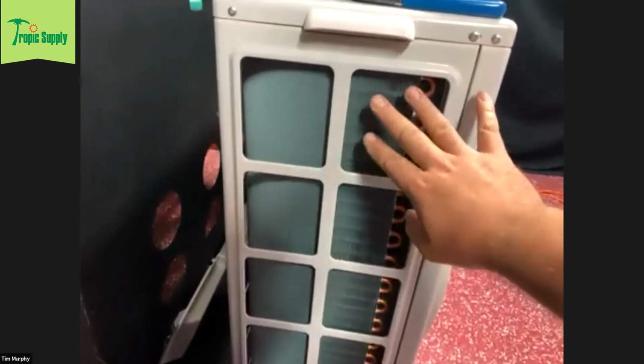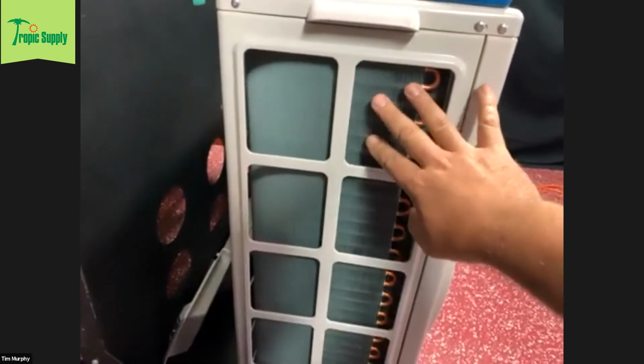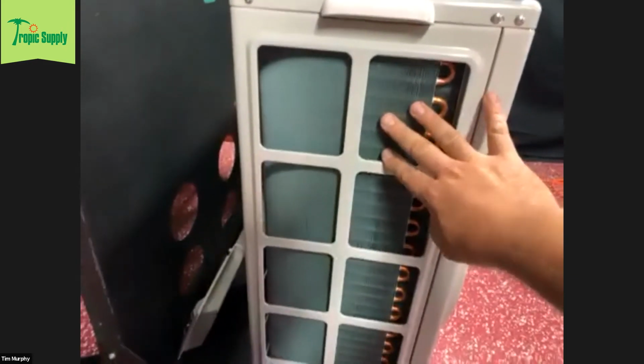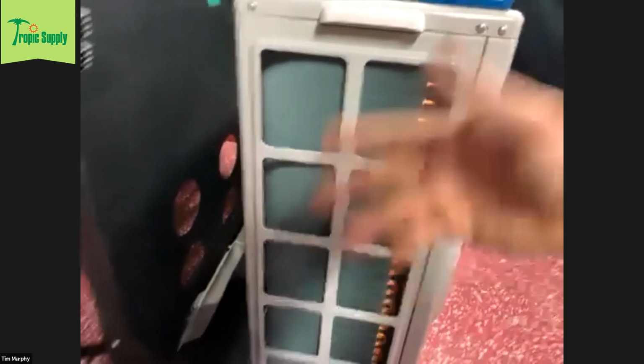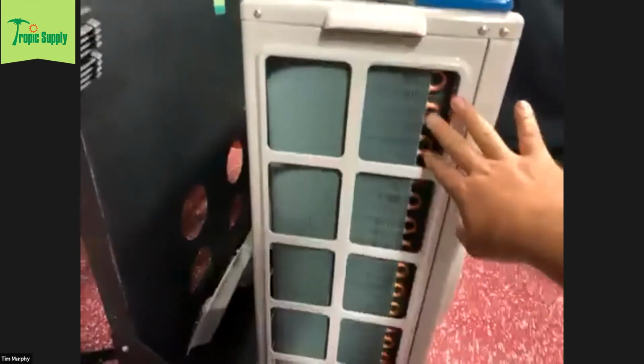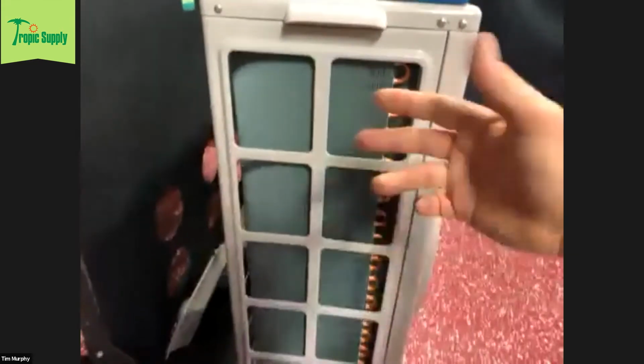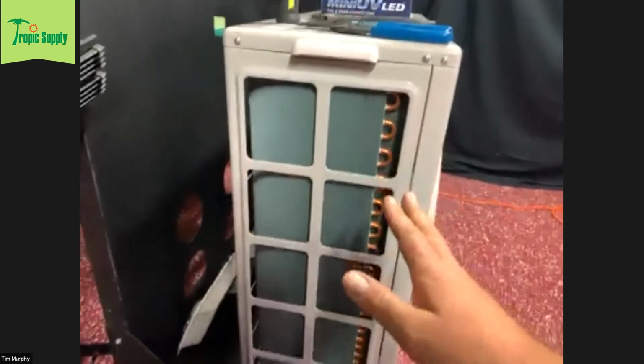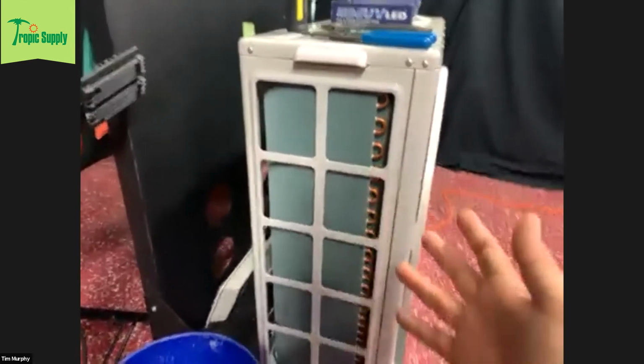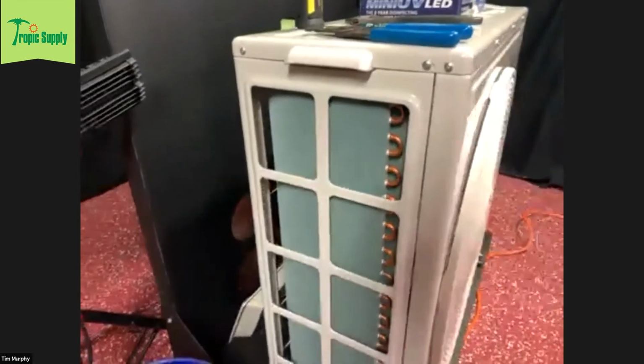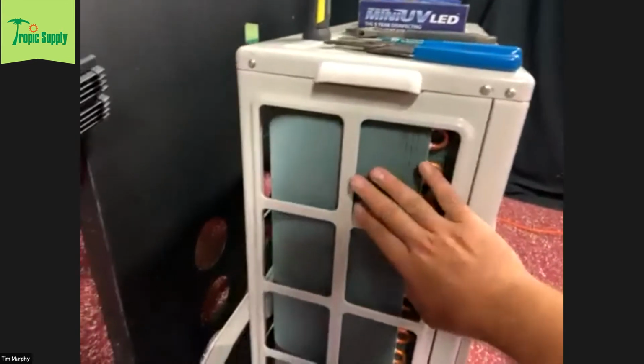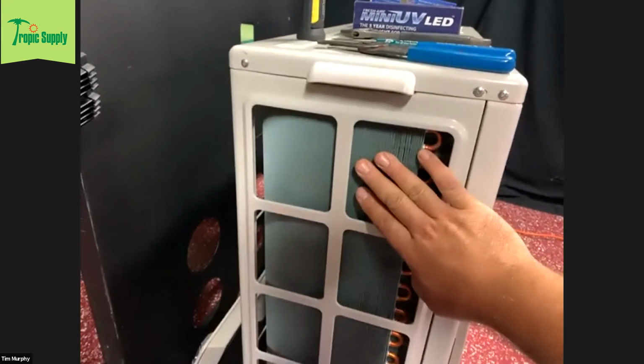From the few I've seen already installed, I haven't seen much corrosion on them. We'll see as time goes on, but it actually has been tested. It's a tested, rated coil to be near the beach. Near the beach is going to have issues no matter what system you put in, because the only thing on these that's coated is the coil.